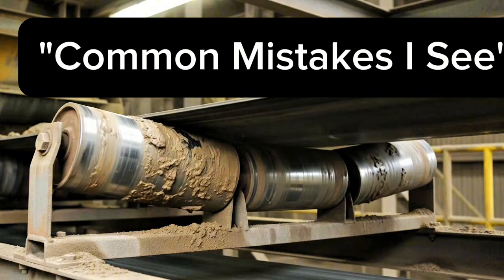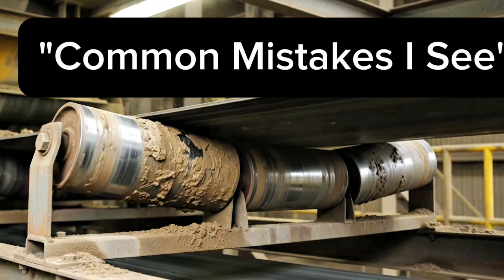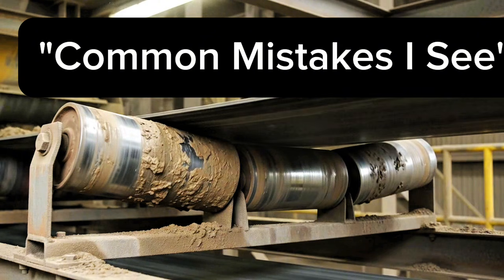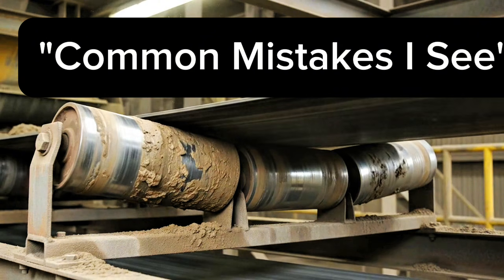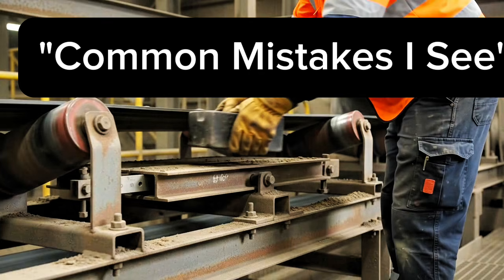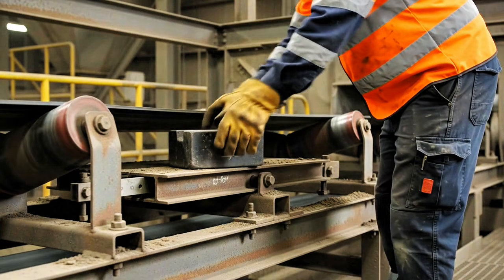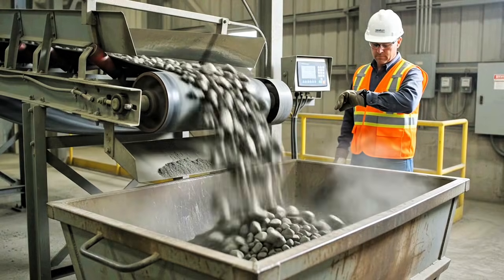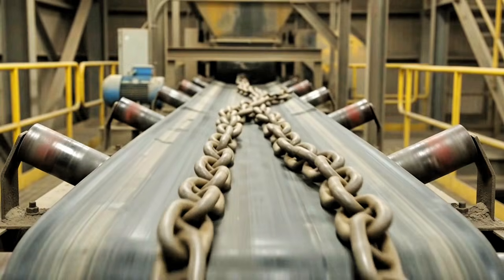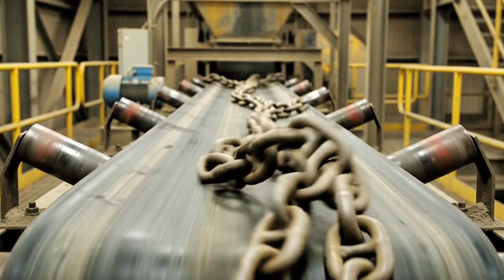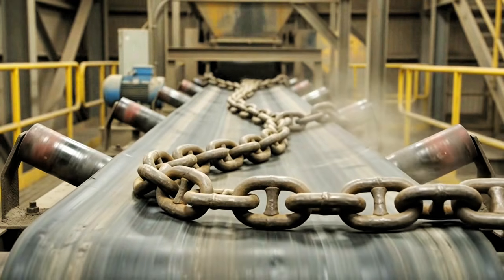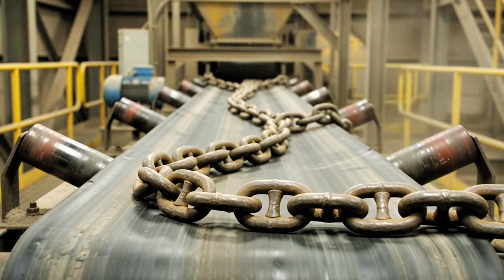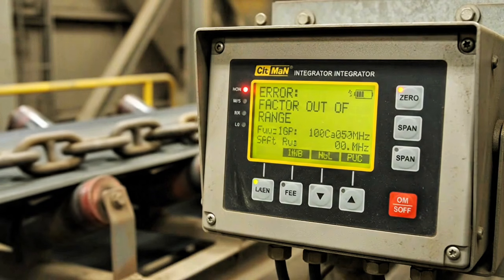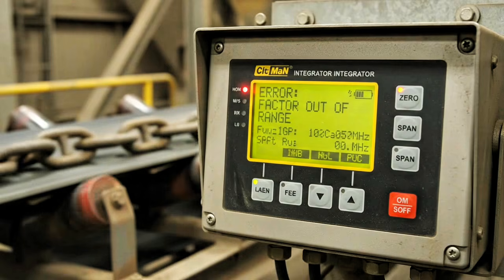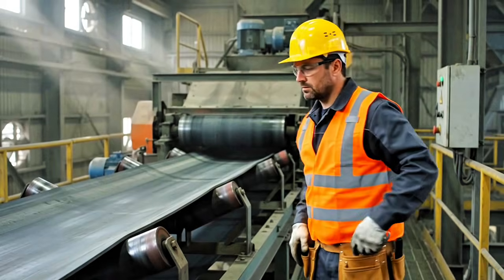Let me leave you with the mistakes that actually happen on real plants. Calibrating with a dirty, material-caked idler and never noticing the tare has shifted. Applying the test weight at the wrong point on the weigh span. Skipping zero calibration and going straight to span. You need both, in that order, every time. Running chain calibration too fast or too slow relative to normal operating speed, which introduces its own error. And the big one, calibrating once at commissioning and then never again, because it was fine when we installed it. A weigh feeder is not a set and forget instrument. Treat it like the process control device it actually is.